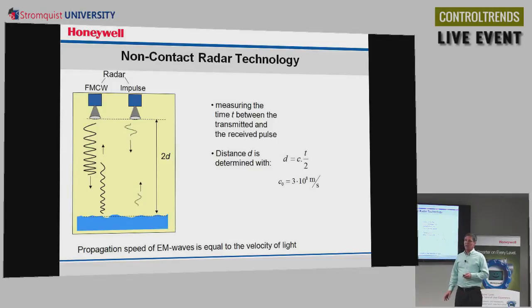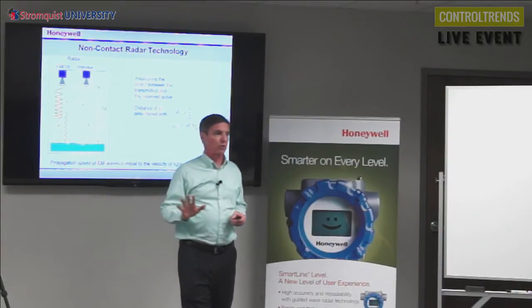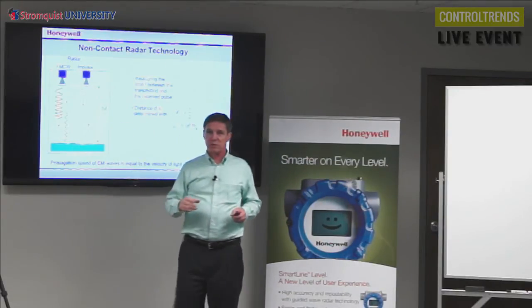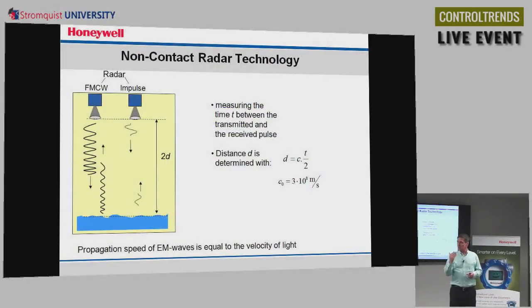Our next technology is radar again, but it's non-contacting. So there's a couple different ways to do this. We have the antenna, and you can use a continuous wave, and that continuous wave just changes frequencies. That's a different technology we really won't talk about today. But that's one way to do it, with the continuous wave. The other way is with an impulse, and we're going to use the impulse method. So this is saying no waveguide, we're going to send this pulse out, and we're going to see how long it takes to go to the surface and bounce back up without the waveguide. Same idea as what we talked about this morning.